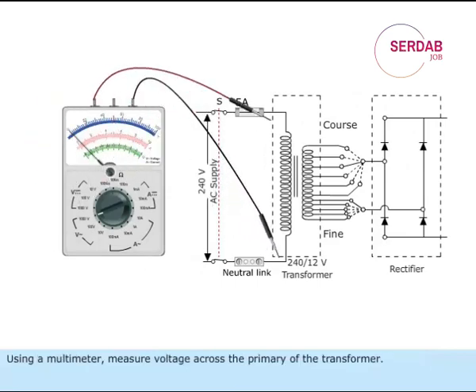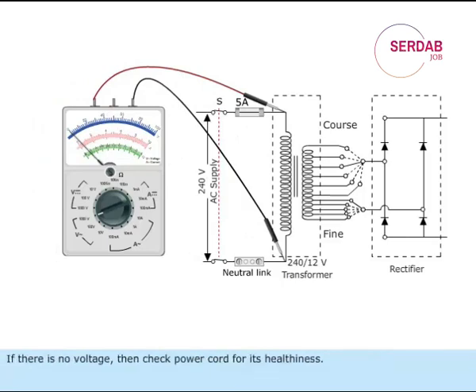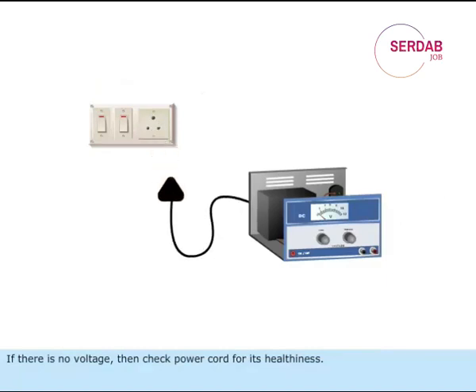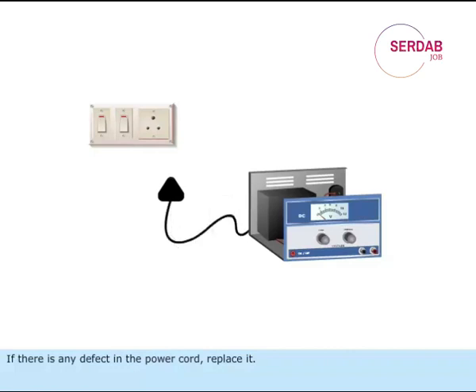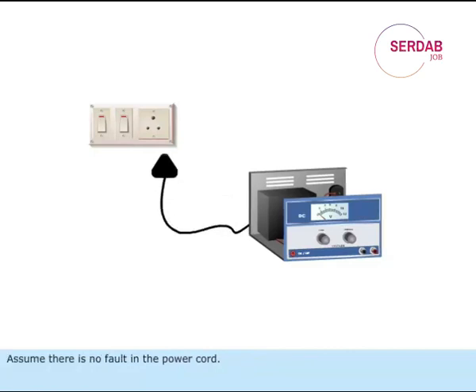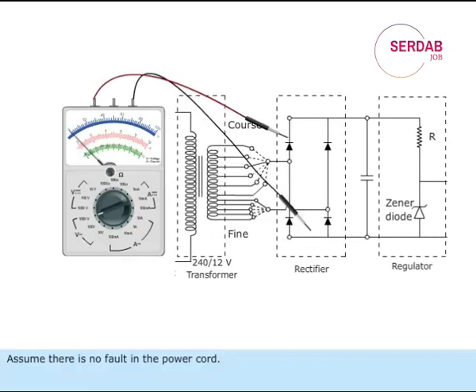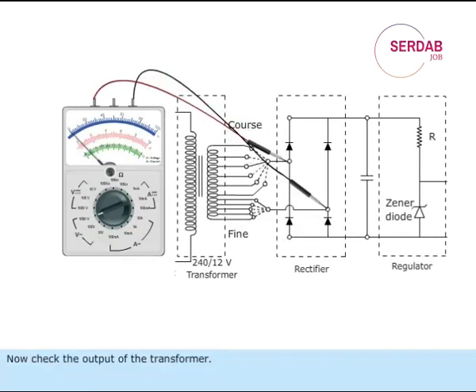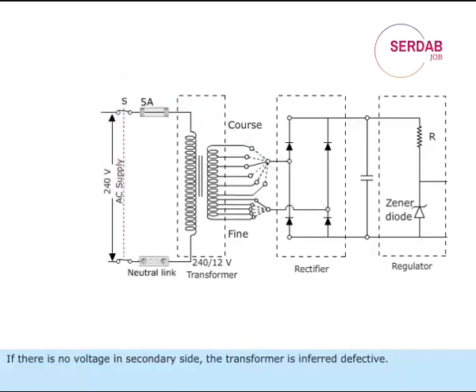Using a multimeter, measure voltage across the primary of the transformer. If there is no voltage, then check power cord for its healthiness. If there is any defect in the power cord, replace it. Assume there is no fault in the power cord. Now check the output of the transformer. If there is no voltage in secondary side, the transformer is inferred defective. Replace the transformer. Assume there is no fault in the transformer.